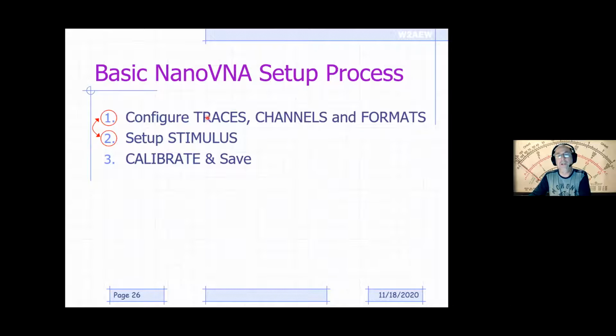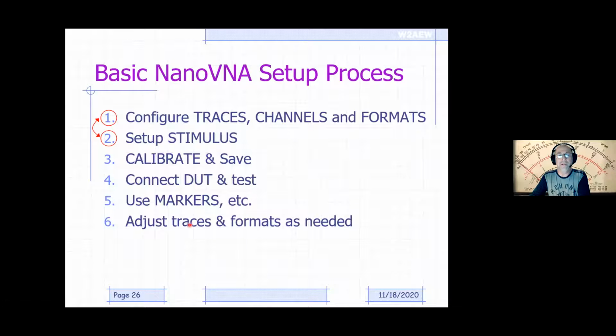And you can even add traces later on, but it's important to do that calibration after you set the stimulus. Then you go off and connect your DUT and make your tests, make your measurements, take a look at what you're doing, etc. You can add markers to get some more numerical results off of those traces, and adjust the traces and formats further if you want to.